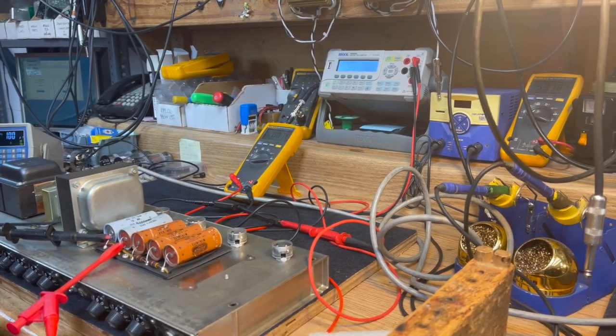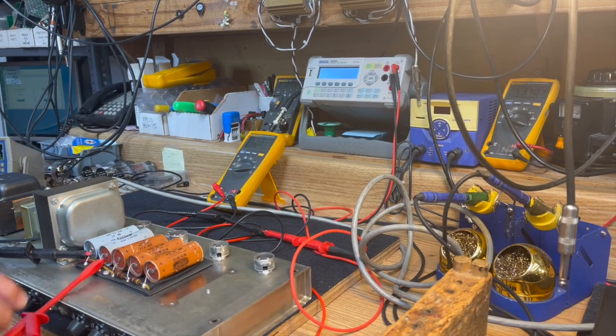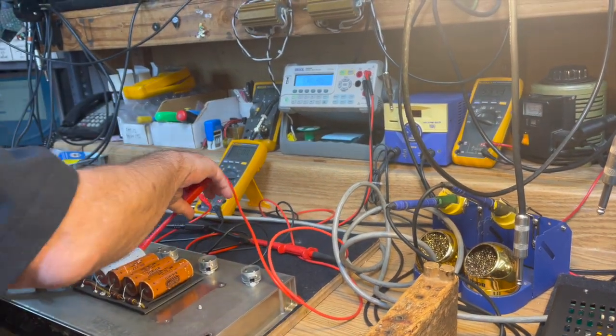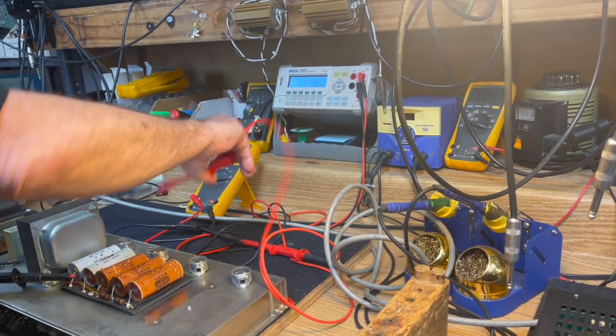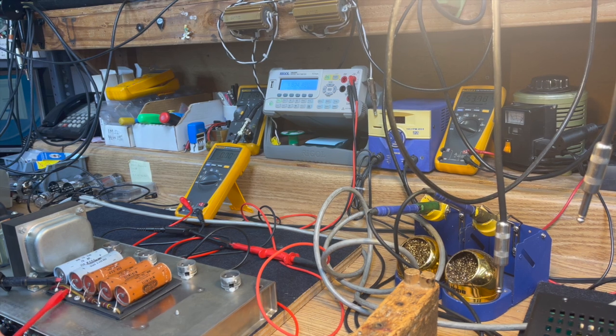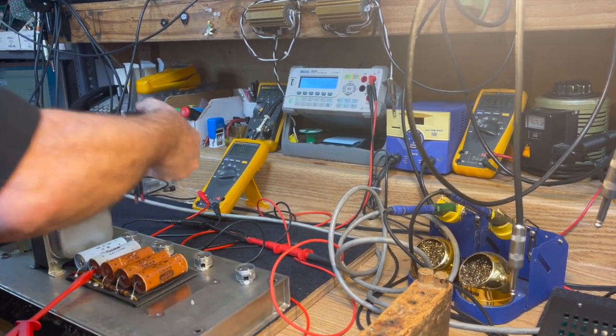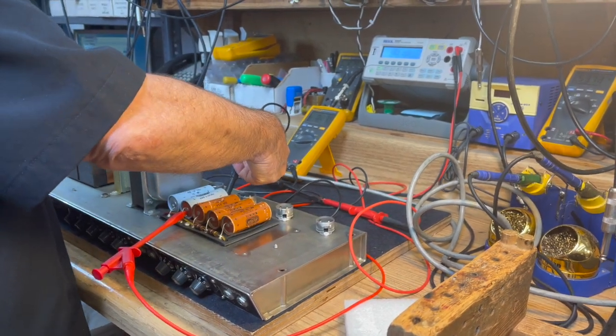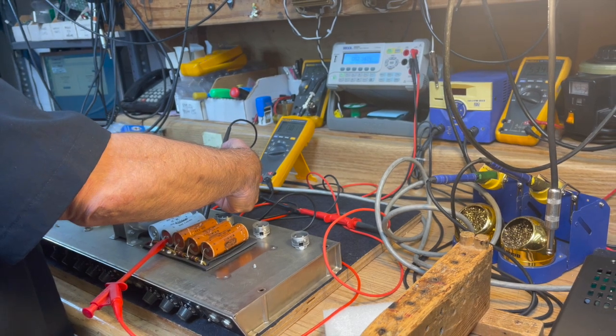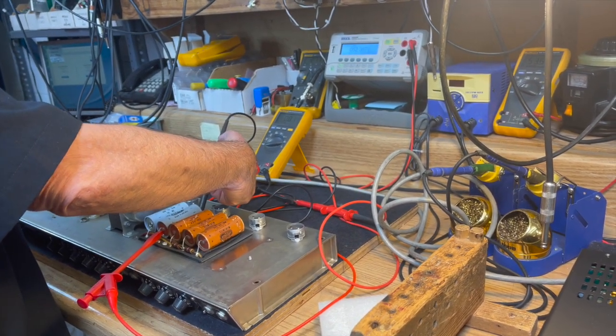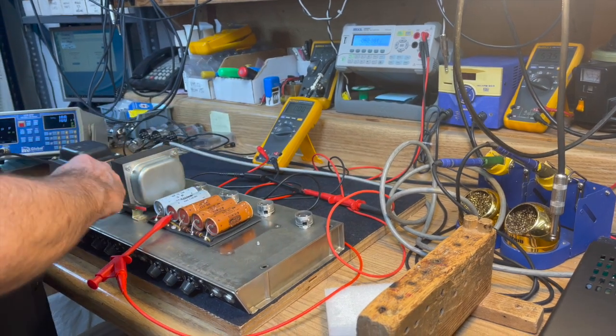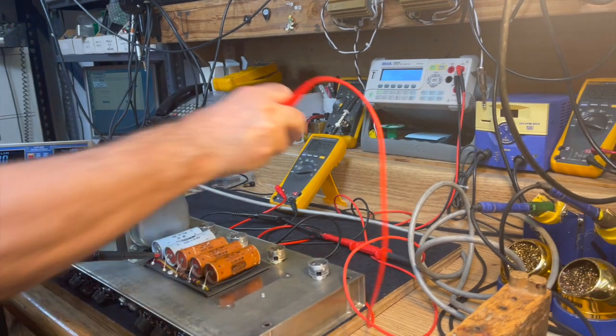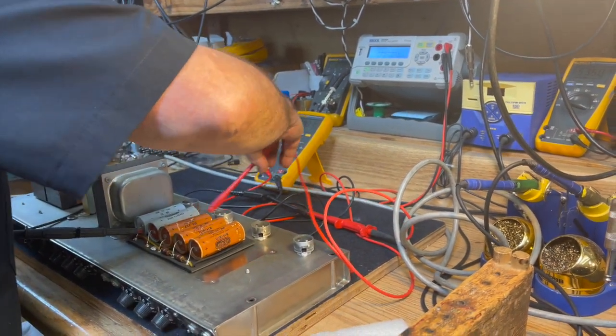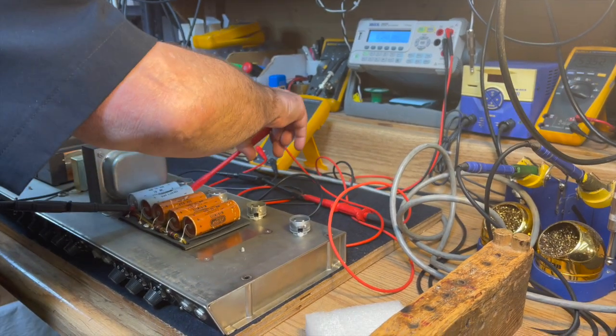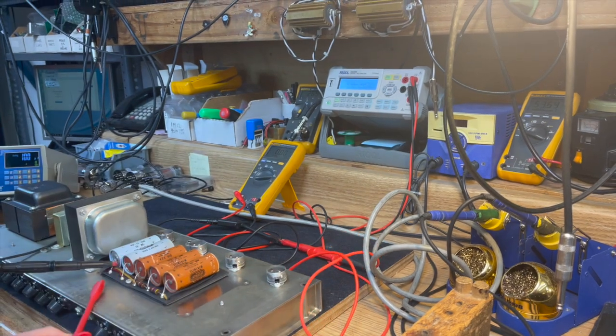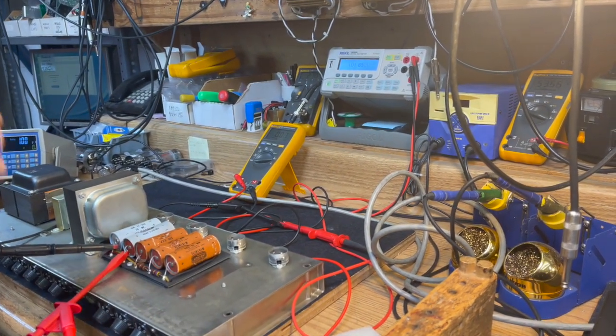So here we are at 100, 101, still 1 milliamp. There's no leakage. Exactly half the voltage between the two caps, which is what you see because of the voltage divider. There are two voltage divider resistors in there that guarantee that each capacitor gets approximately half of the voltage across the two series pairs. So there's 52 on the top leg capacitor, and 48 on the other one. Totally acceptable.